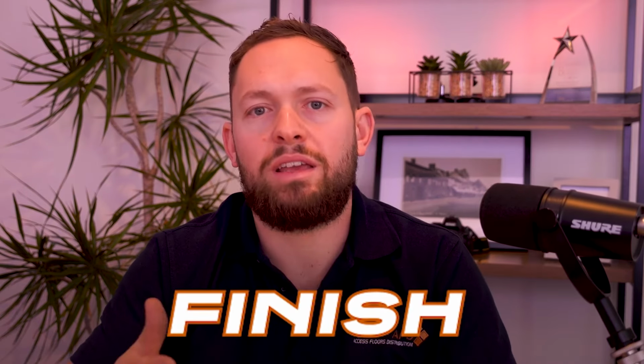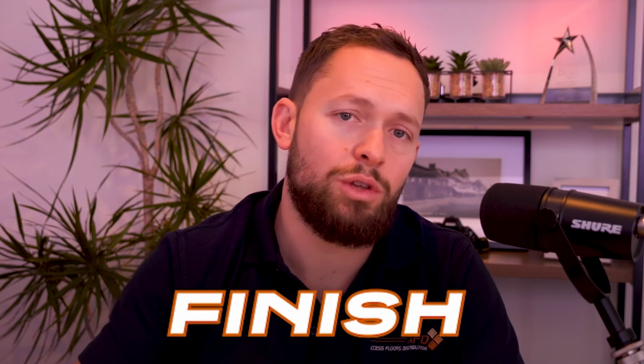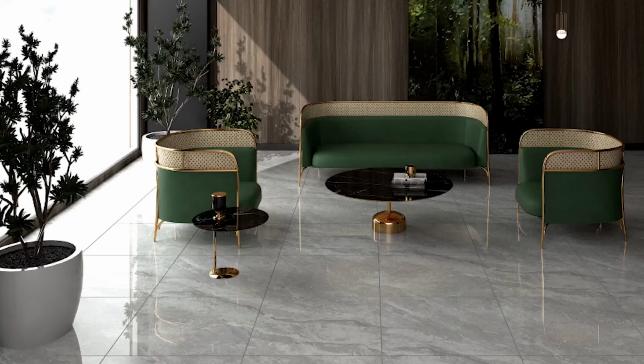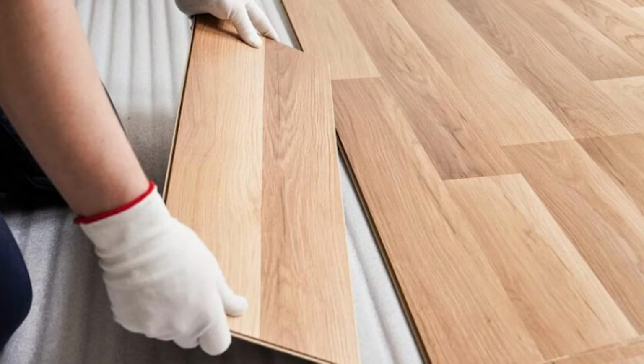I believe that making the right decision in terms of choosing the correct components for the raised access floor system or hollow floor system comes down to the finish. What is ultimately going to be installed on the floor as the finish helps dictate which system you would lean towards. It doesn't make sense to me to install an accessible raised access floor system when you're looking to apply a continuous finish. So continuous finish would be maybe a porcelain tile or a terrazzo tile or a vinyl or an engineered wood, for example.